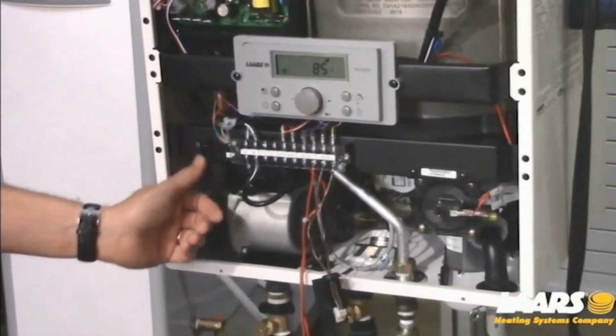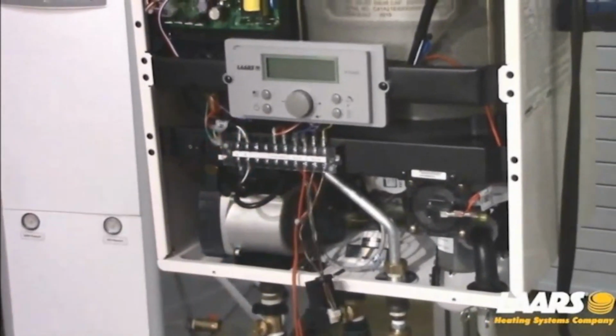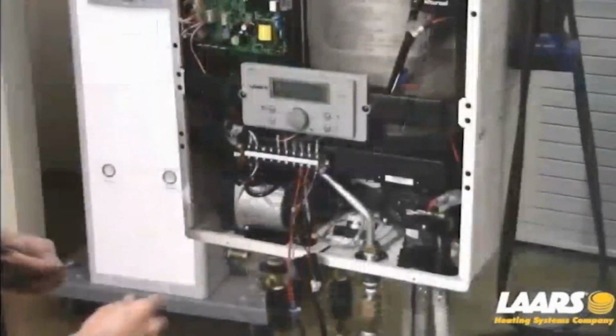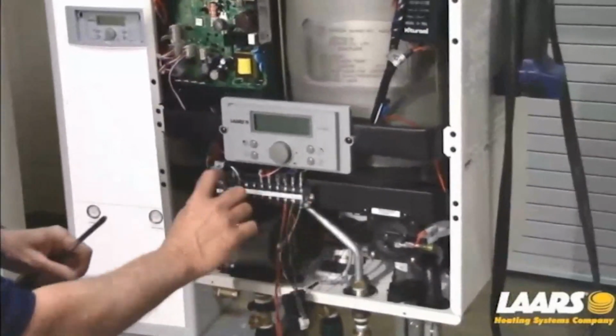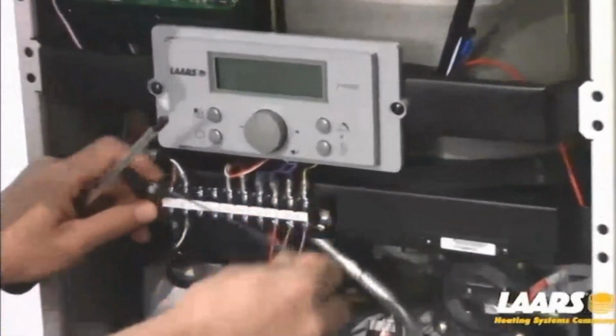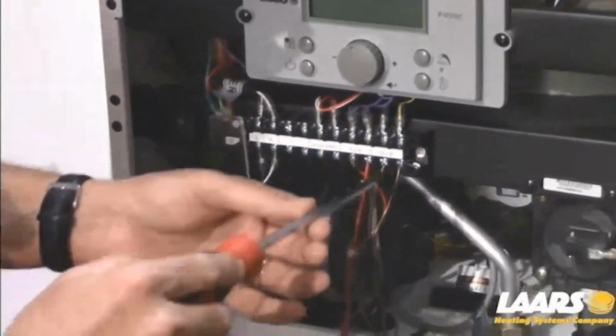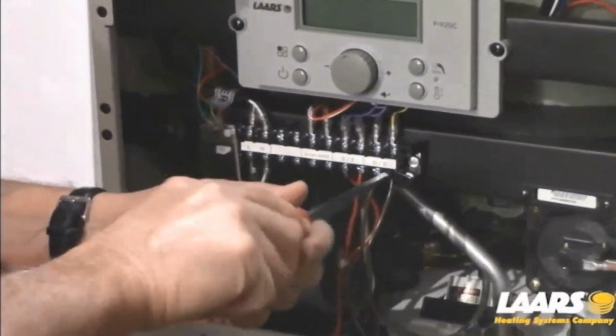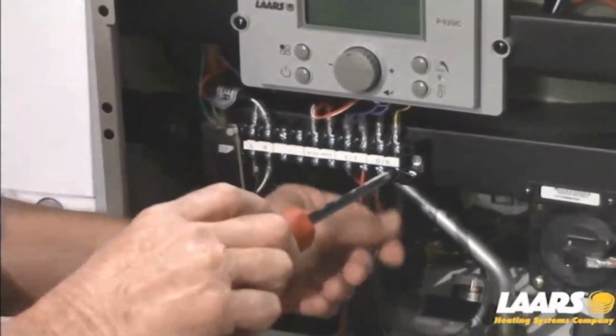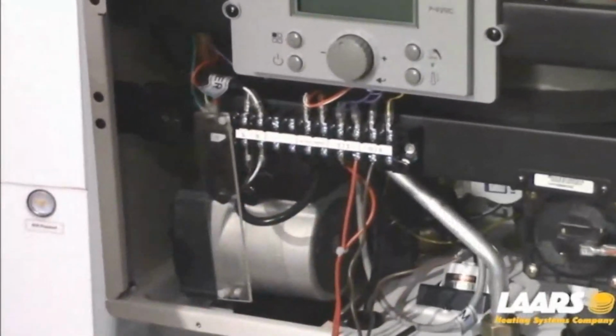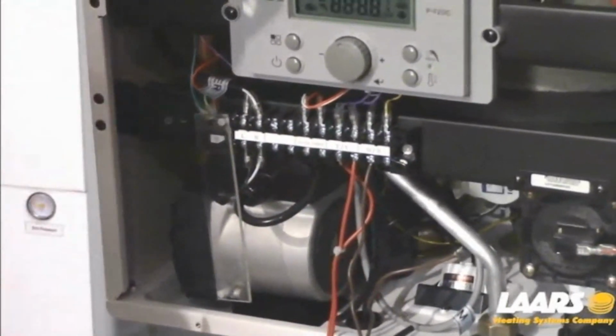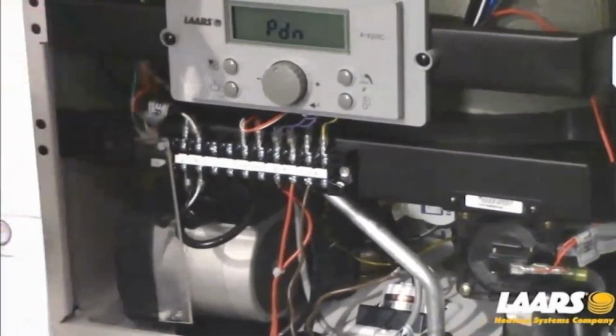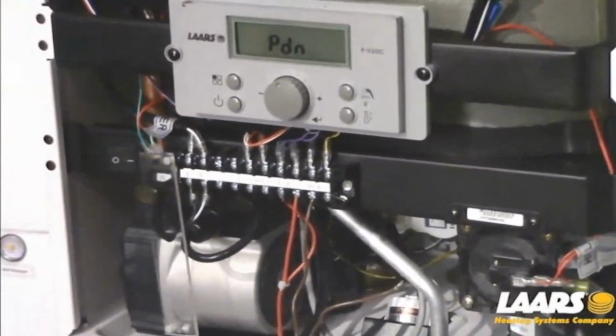So very simply, I'm going to power the boiler off. I'm going to disconnect one of the outdoor reset wires. To remove the outdoor wire, we have a plastic cover. Simply pull forward. I'm going to slide that down and remove one of the outdoor reset wires. With that disconnected, I'm going to power the display back up, or the boiler back up, and we'll go through a sequence.